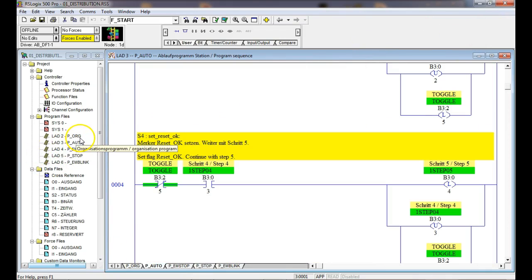So subroutines, everybody. I know Jobert hadn't had that, but he understood it pretty well. But y'all understand that. So what do subroutines do for us? Well, that's a point, and that's true. But the main advantage of subroutines is it gives us the ability to divide the program up into modules. Each module has a task. So if I have problems with a task, I don't have to go into a program and look through 500 rungs. I go to the subroutine that handles that task. Does that make sense?